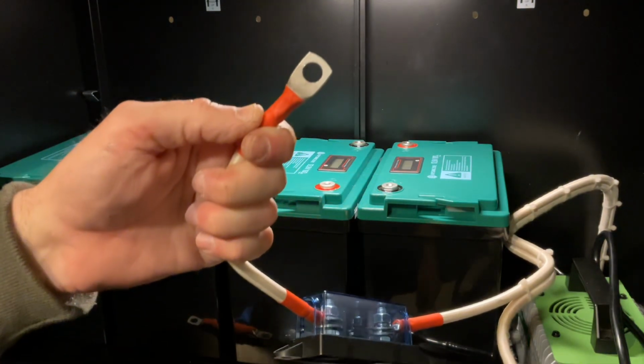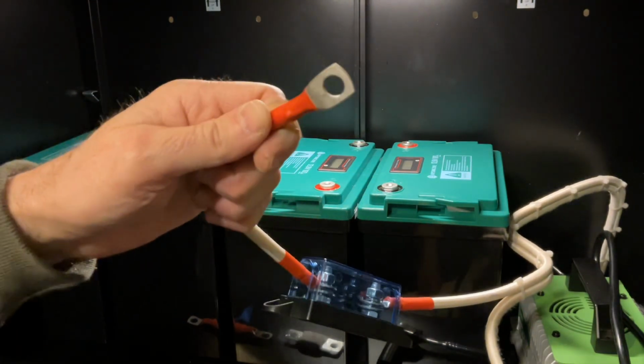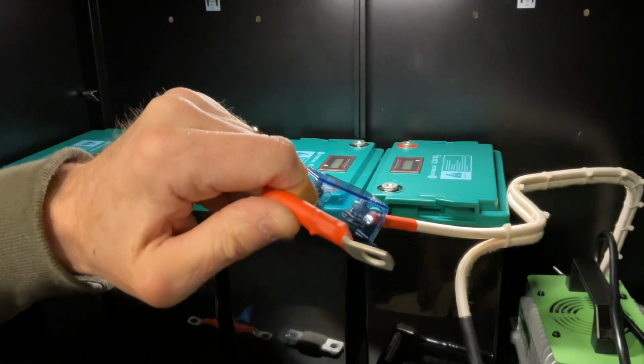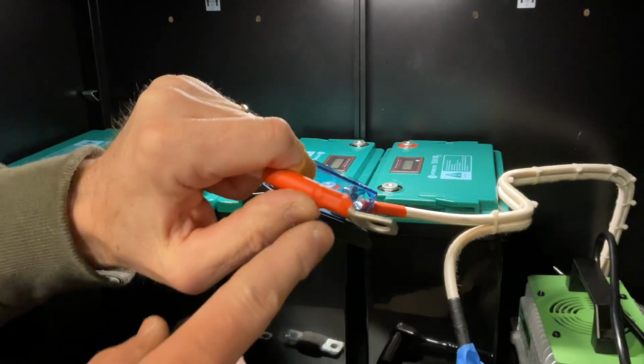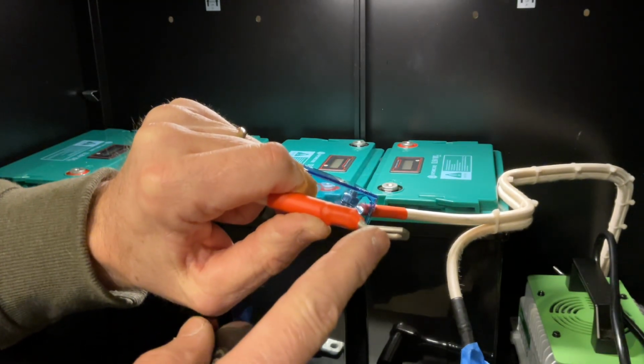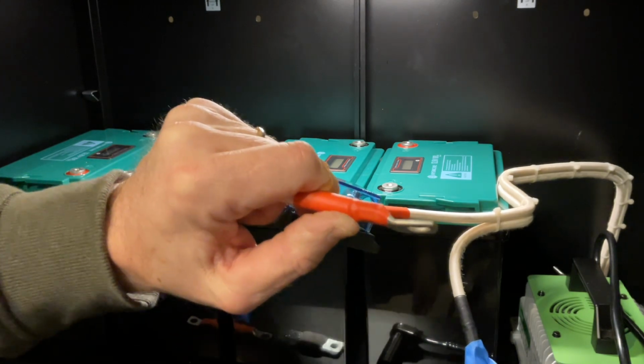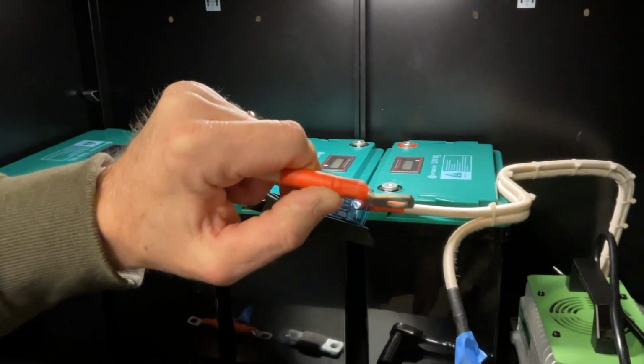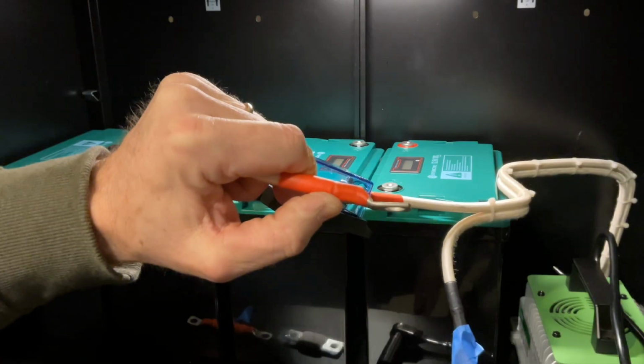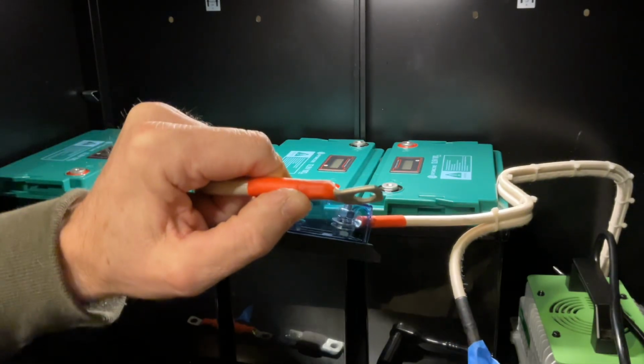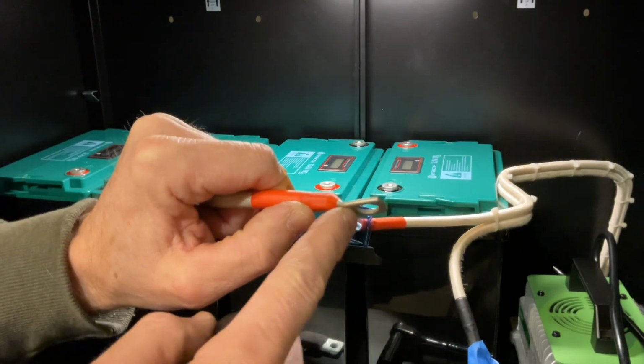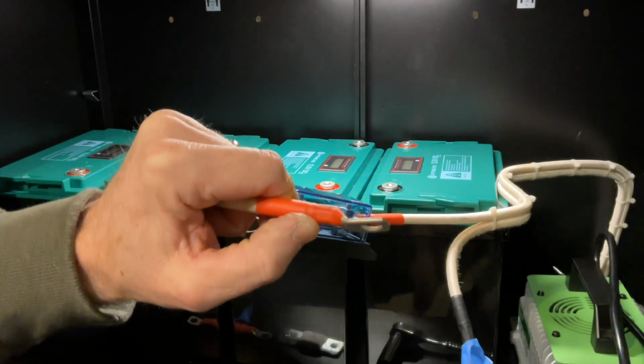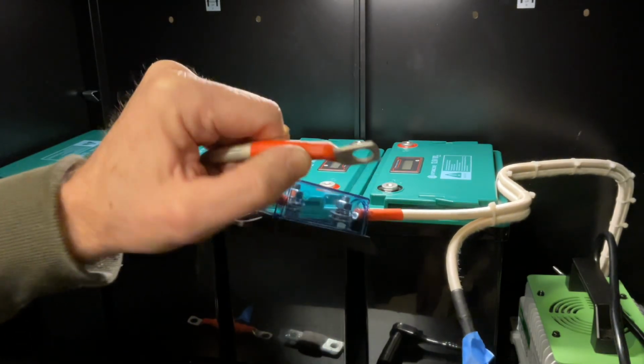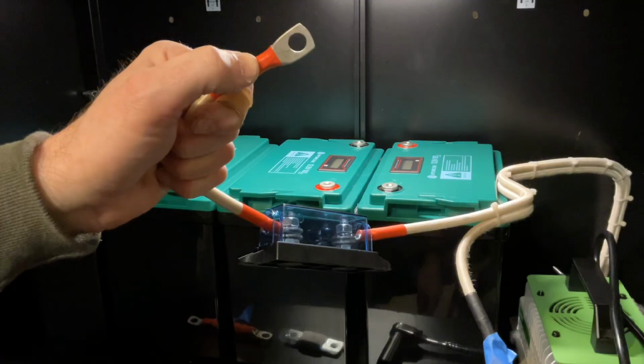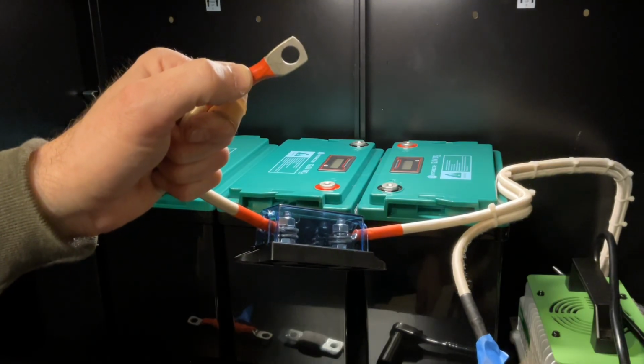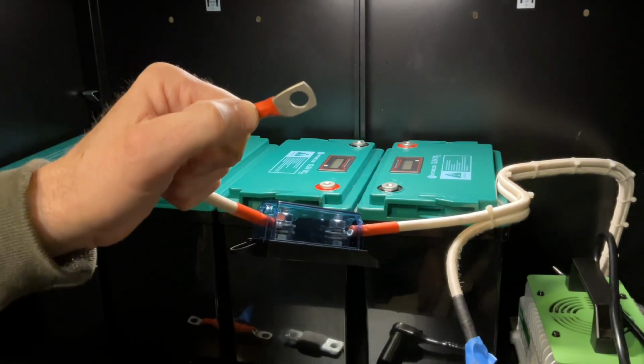Something you want to watch out for when you terminate your terminals on your cables and put heat shrink on: make sure the heat shrink does not protrude out underneath the contact area. Will Prowse and several others on YouTube are good at pointing that out, since when they take apart batteries they find the heat shrink under the contact area of the terminal and trim it back to ensure a positive connection. Watch for that so your heat shrink does not extend into the contact area of your terminal.